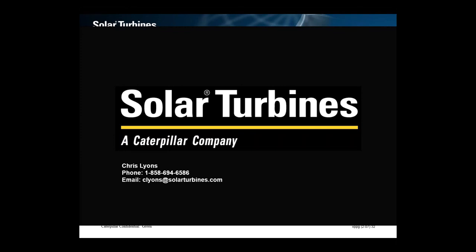Yeah, that's a good question. We're actually just commissioning right now 3 Mercury 50s burning digester gas in Washington, D.C. at the wastewater treatment plant. We've had the Los Angeles County wastewater treatment plant in operation continuously for almost 30 years. It has 3 of our 10 megawatt turbines. What they do there is use water injection to reduce the NOx, because in that particular engine, the heating value is too low. It can't be burned in a dry, low emissions combustor. The Mercury 50, because it's recuperated, can burn landfill and digester gas.